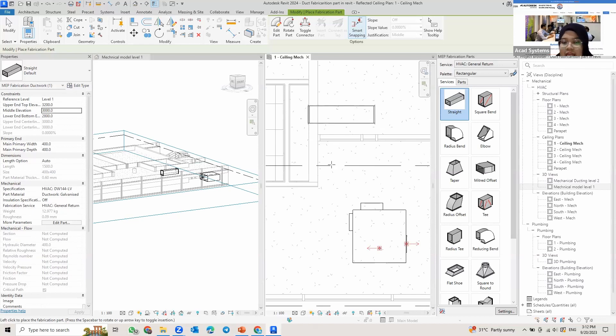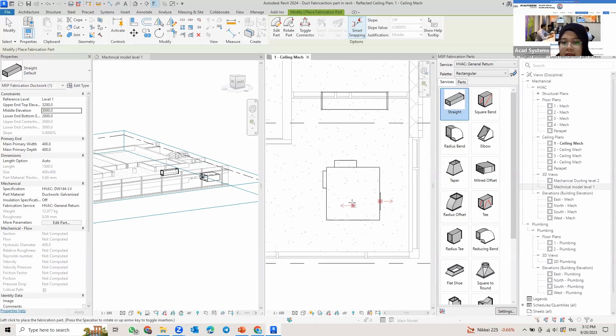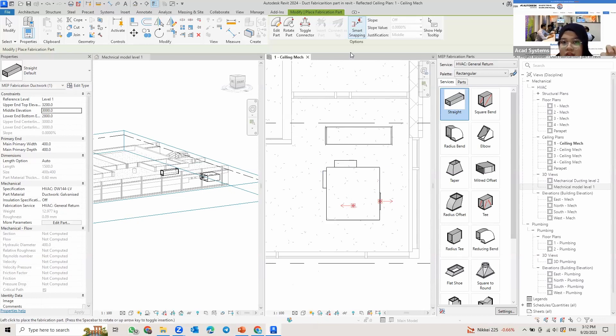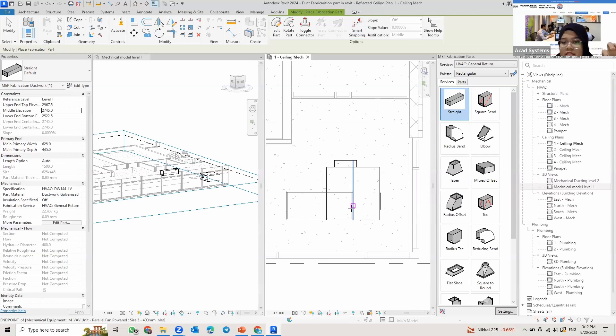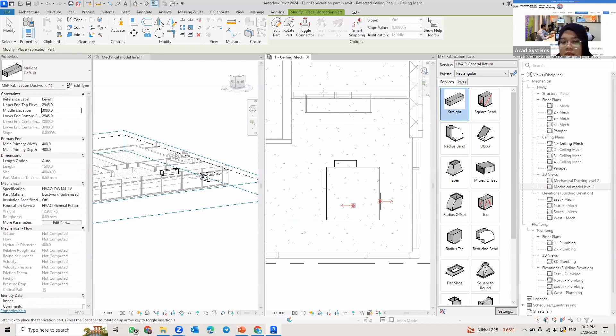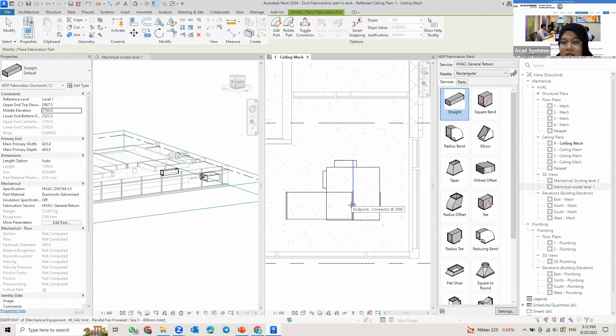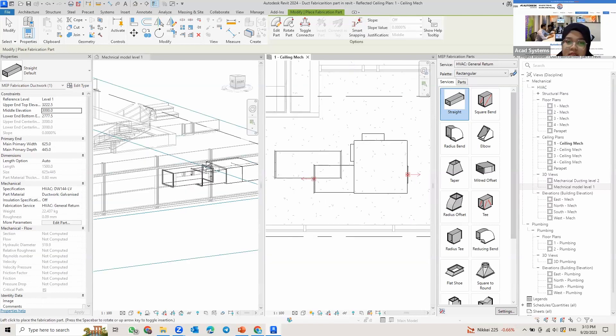For the sizes, usually it will automatically refer to the origin. I have this connector which has its own dimensions. To link to this connector, you need to click on Smart Snapping up here. Close on this one and bring it to the connector. You can see the ducting size changes to the connector size. If I don't bring my cursor to the connector, it stays at the default 400 by 400. But if I bring my cursor to the connector, it follows the connector size. If I place on that one, you can see the ducting in the 3D view.